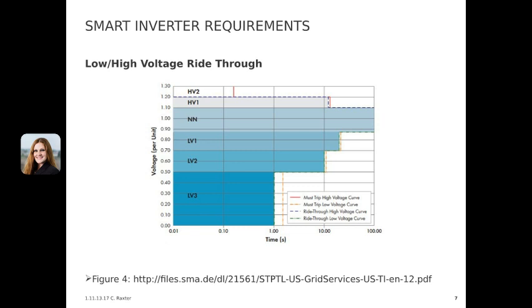The intent with this setting is to prevent brief interruptions, like 160 milliseconds, which could cause catastrophic cascading events. To explain that a little further, if you have more than 10% of PV penetration on your utility grid, and you have a slight voltage bump or voltage drop, then having all of that PV turn off instantaneously could cause a lot of stress on the generators that are connected to that vicinity, and could cause those generators to trip offline, which could potentially cause a cascading event where you get rolling blackouts over a long period of time.